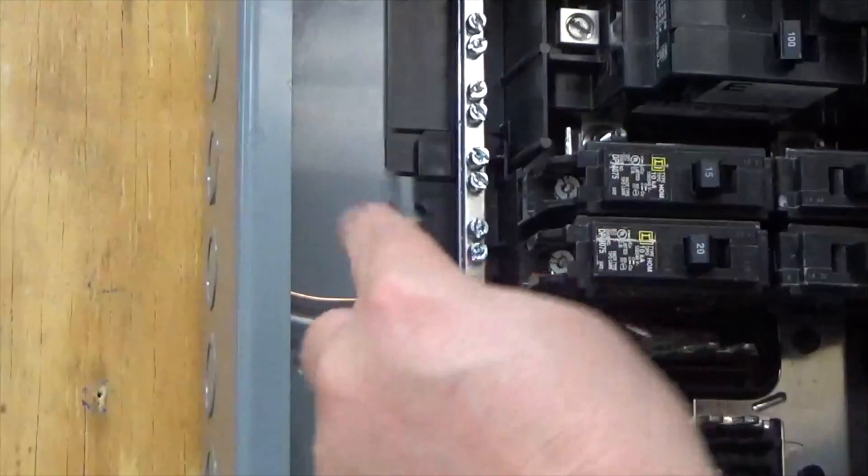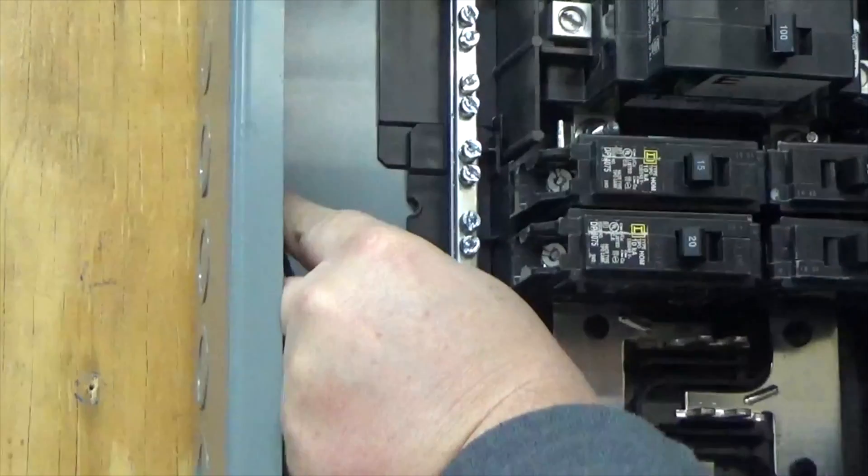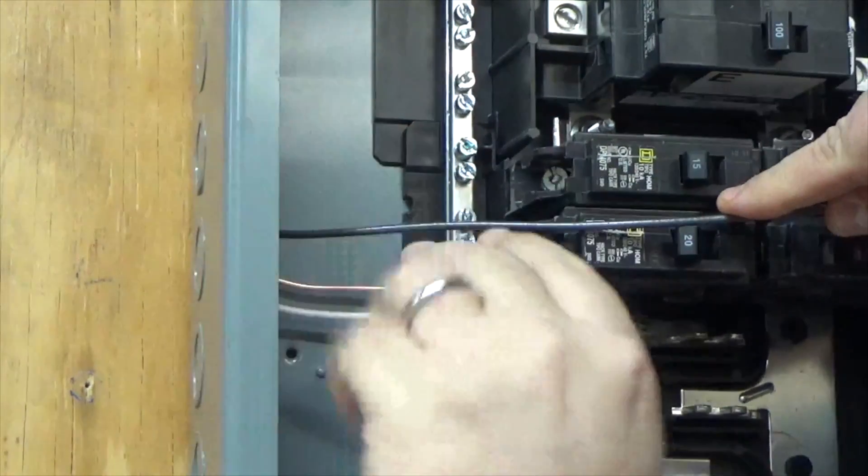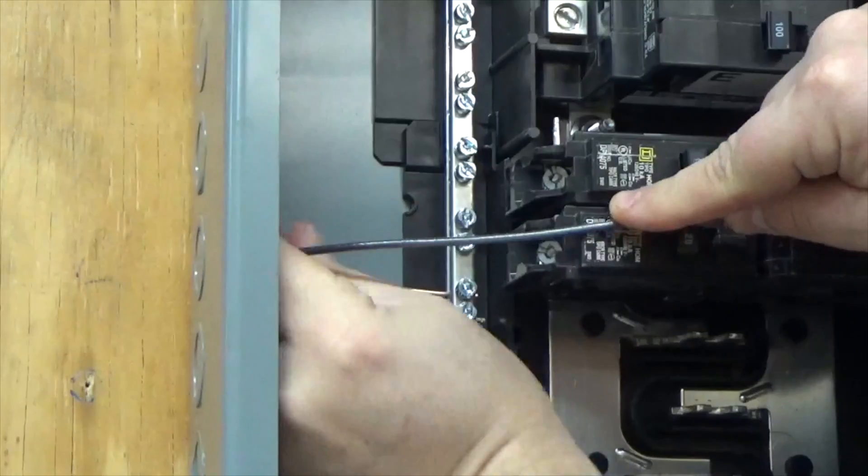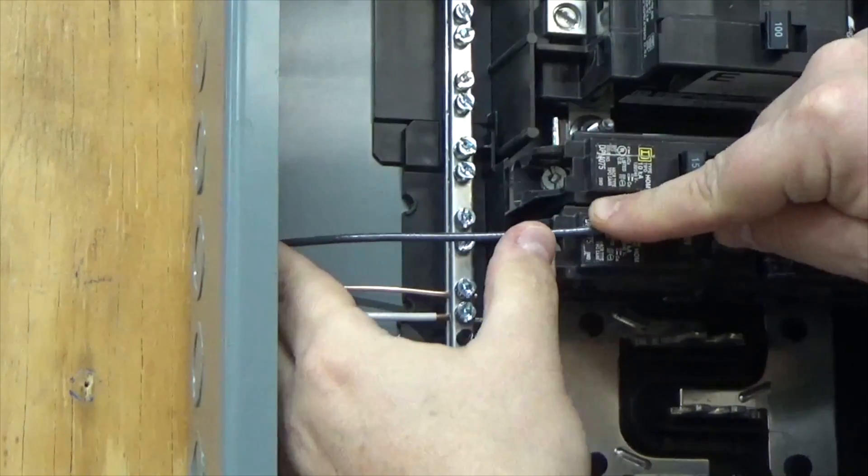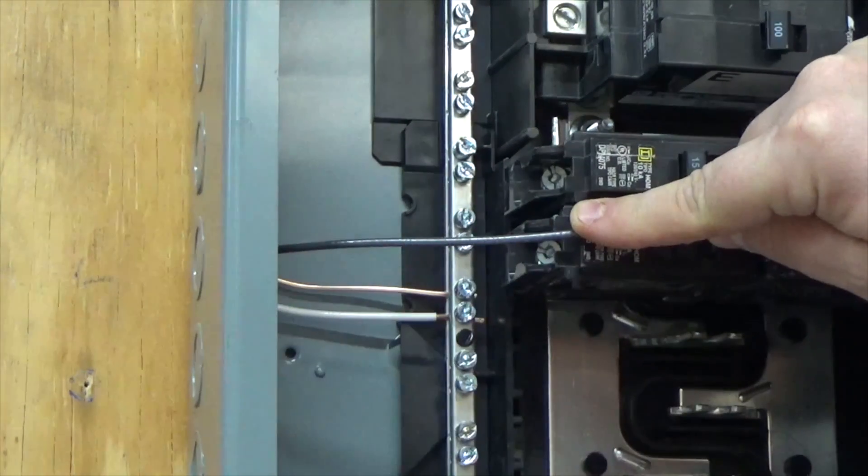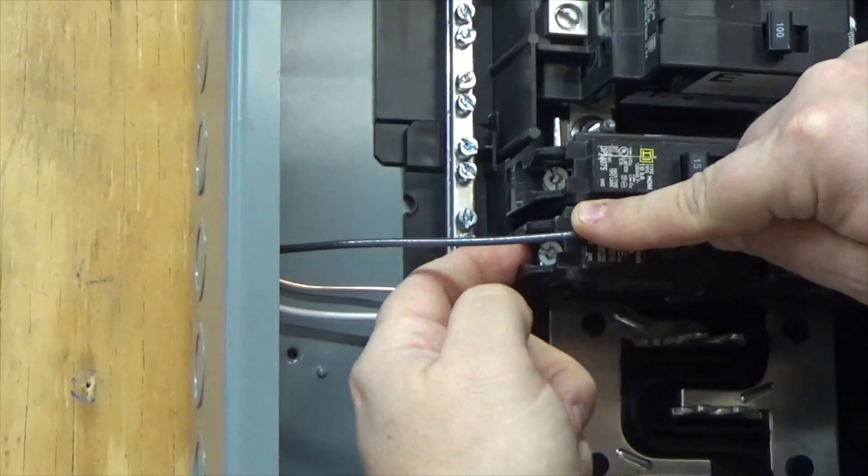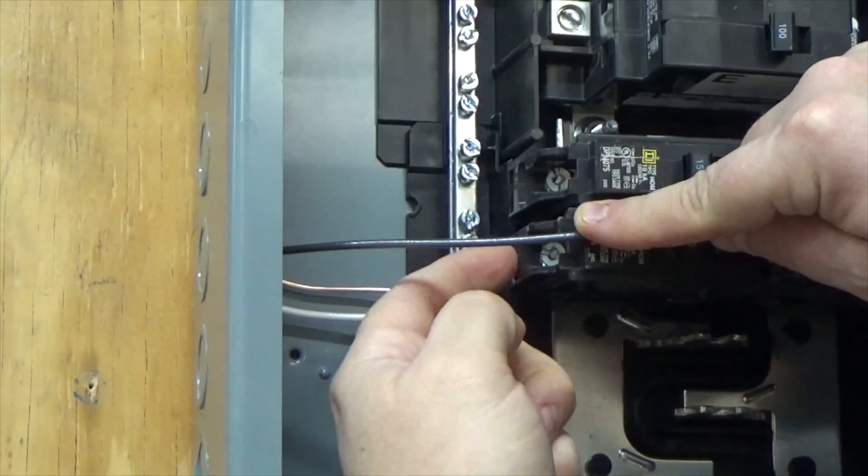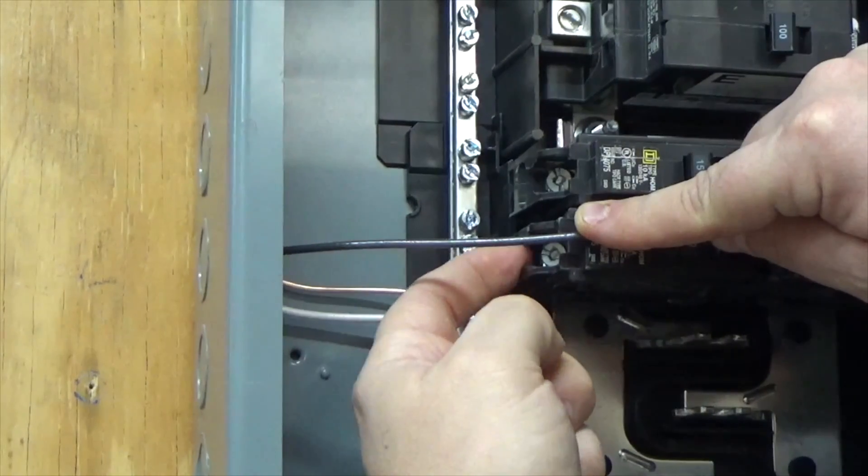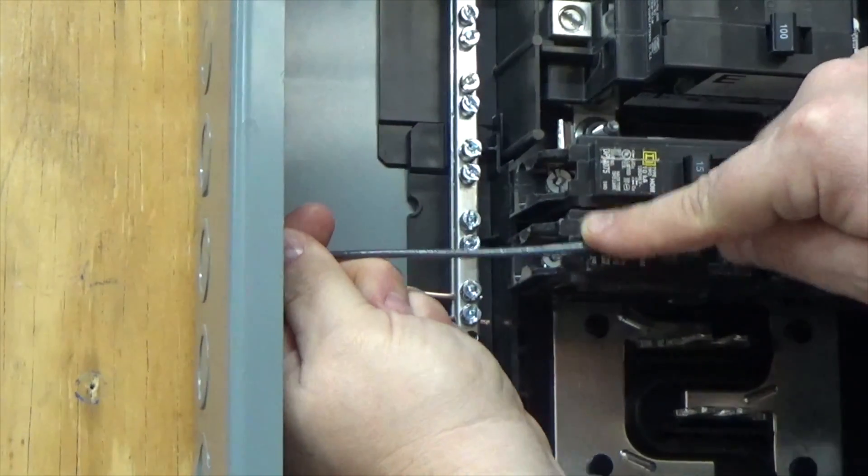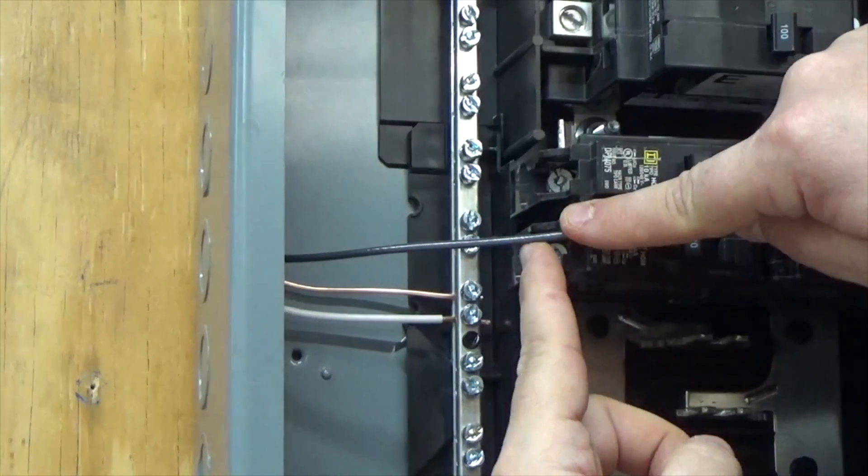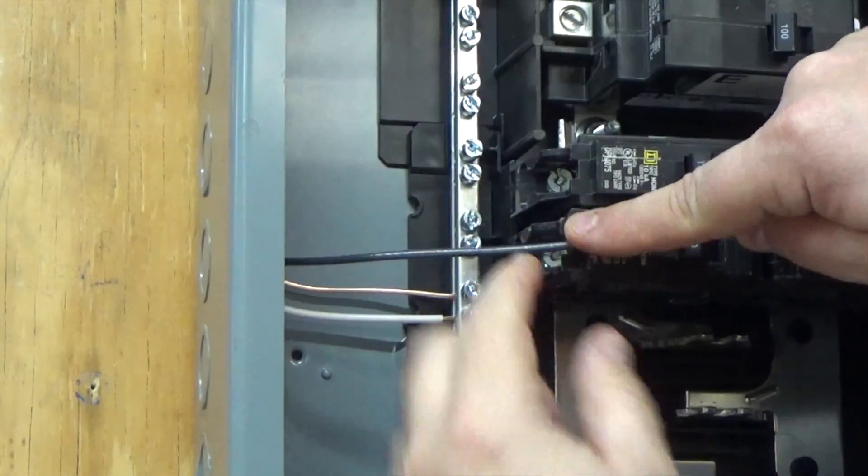Now I'm going to take my black conductor and I'm going to follow the same path. I'm going to come through and give it a little bit of a bend. Now my rule is when I give it a little bit of a bend, where I'm actually connecting it is about an inch and a half up from the back of the panel. So about an inch and a half I'm going to give myself a little bend. Then right about where the wire meets the breaker I'm going to cut it.